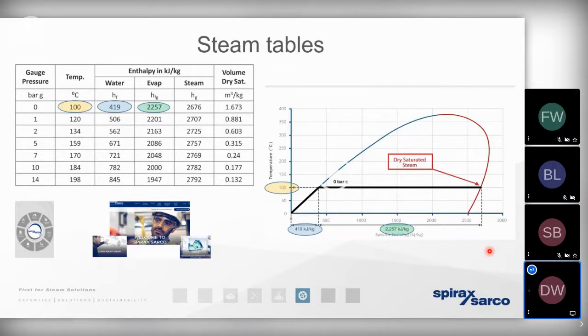We've got the other issues we've spoken about previously. Wet steam, more condensate. If we've got more condensate, we need to install and maintain a greater number of steam traps, and we're exposing ourselves to a greater risk of that erosion, corrosion, and water hammer that we've spoken about previously. But that steam that's passing across a trapped film of condensate in the bottom of the pipework, it's going to have its energy level further degraded. So we get a greatly reduced mass of steam finding its way to the process. But the steam that does manage to find its way to the process, it's going to have less energy contained within it as well.